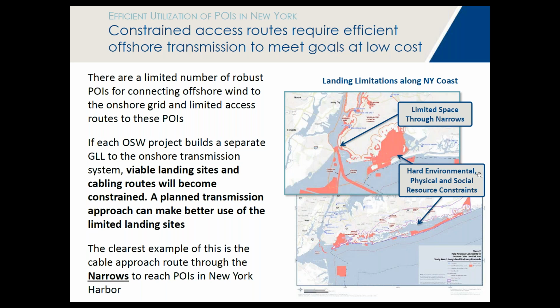In the long term, there's a limited number of landing sites for offshore wind transmission in both New England and New York. If each offshore wind project requires a separate cable connection to the onshore transmission system, the viable cabling routes become really constrained. This increases the value of planning, because you can identify the capacity of each onshore point of interconnection and make sure you build transmission to maximize that capacity. Otherwise, you get a piecemeal approach that doesn't fully optimize the available capacity of the best points of interconnection.